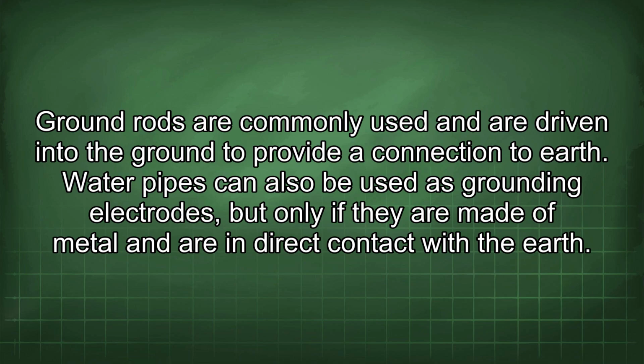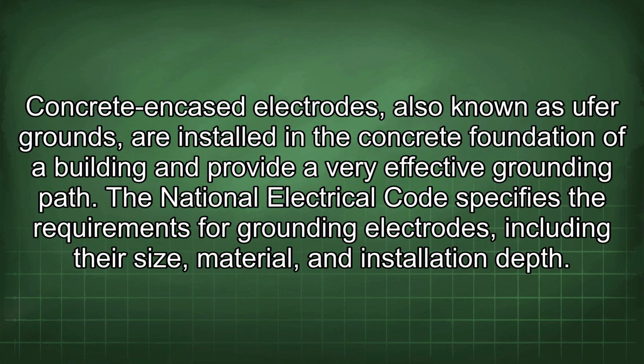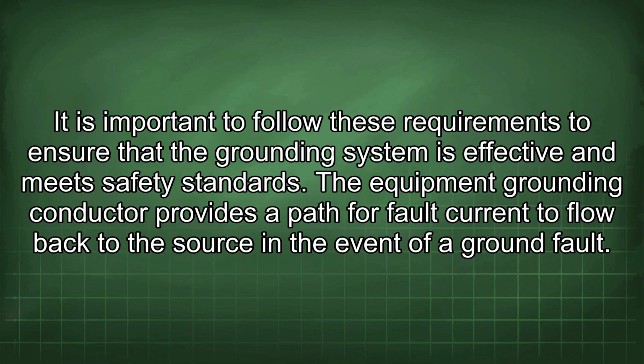Ground rods are commonly used and are driven into the ground to provide a connection to earth. Water pipes can also be used as grounding electrodes, but only if they are made of metal and are in direct contact with the earth. Concrete encased electrodes, also known as UFER grounds, are installed in the concrete foundation of a building and provide a very effective grounding path. The National Electrical Code specifies the requirements for grounding electrodes, including their size, material, and installation depth. It is important to follow these requirements to ensure that the grounding system is effective and meets safety standards.